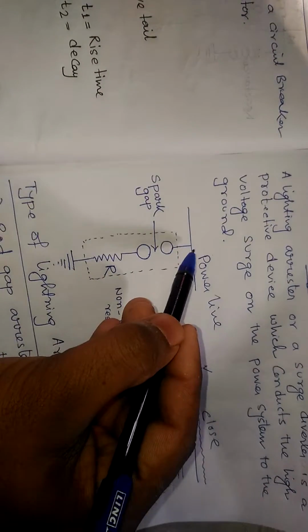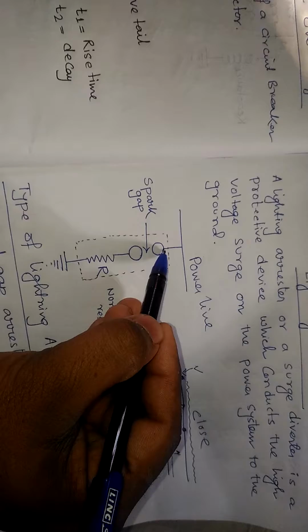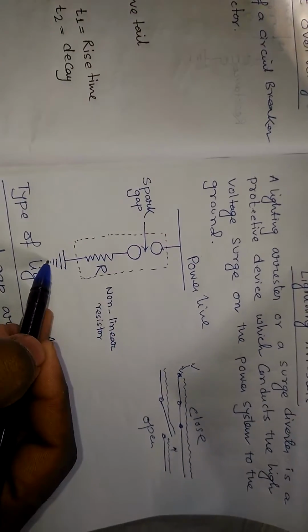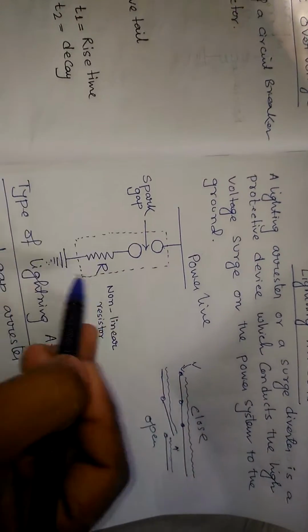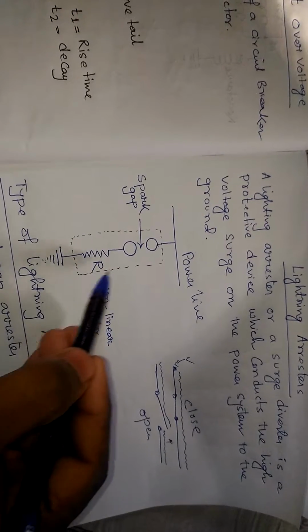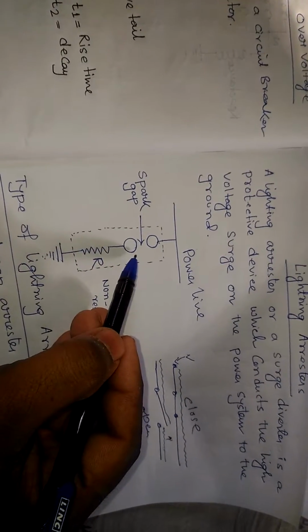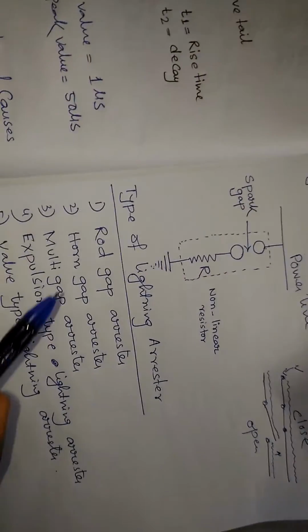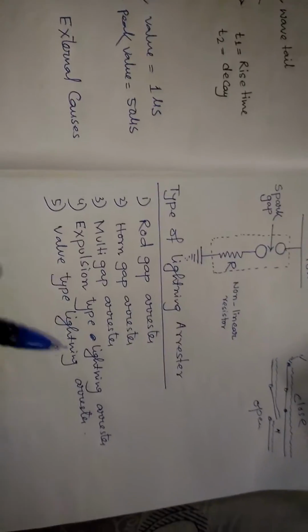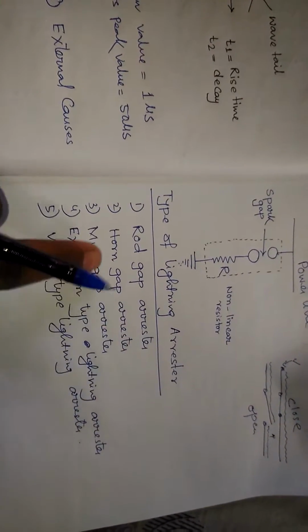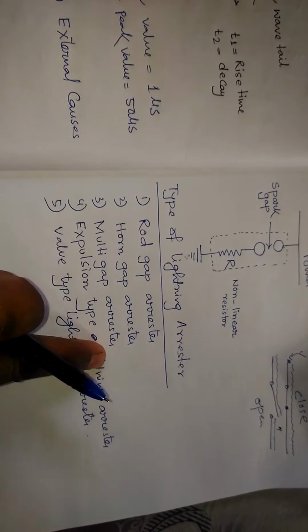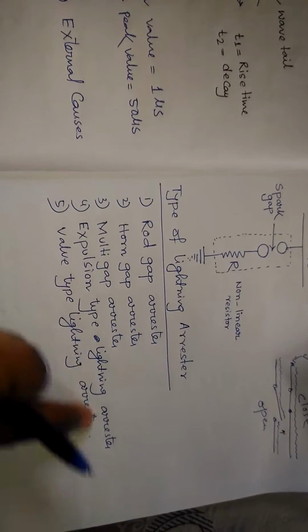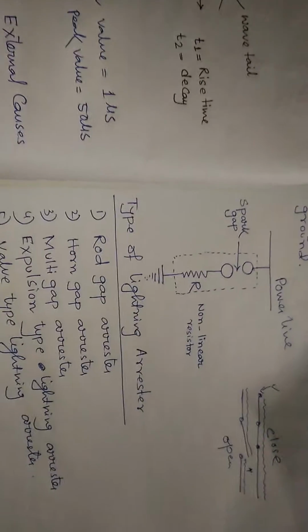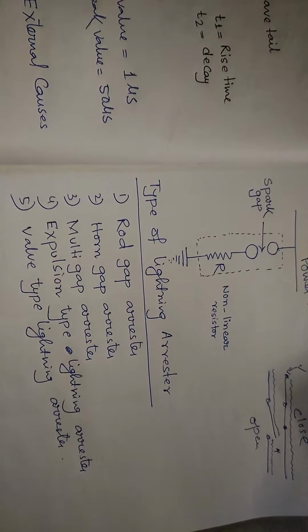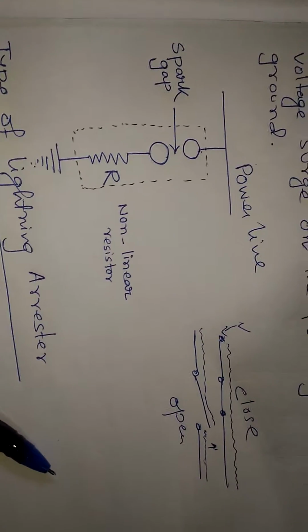We directly connect the lightning arrestor, one terminal to the power line and the other terminal to the earth. In between these, we use a resistance, and this is the spark gap. And what are the types of lightning arrestor? The rod gap lightning arrestors, horn gap lightning arrestors, multi gap lightning arrestors, expulsion type lightning arrestors, and valve type lightning arrestors. Now we have discussed the lightning arrestors.